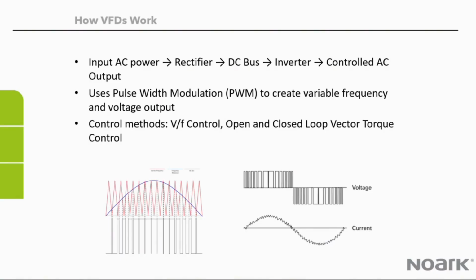How VFDs work. Basically, AC input power comes into the drive, goes through a section called a rectifier, to a DC bus, to an inverter, and that goes to the output of the drive and controls the output. Normally on your input, you're used to something that looks like this, AC for voltage and current. Through all the processing that's done in the drive, this is what comes out as far as the voltage out to the motor, and this is what comes out, relatively, for the current.